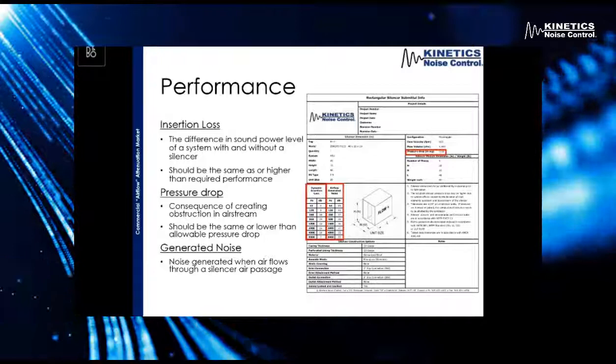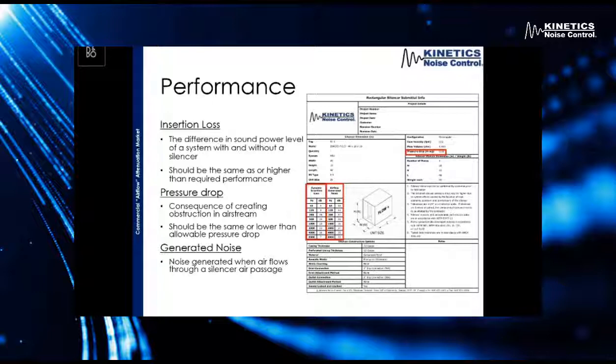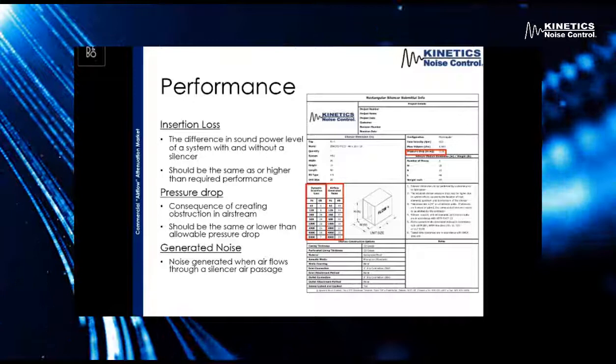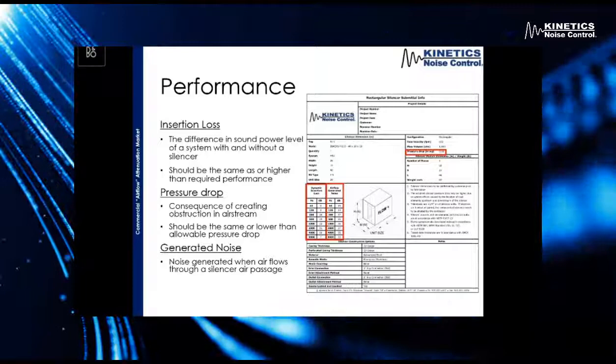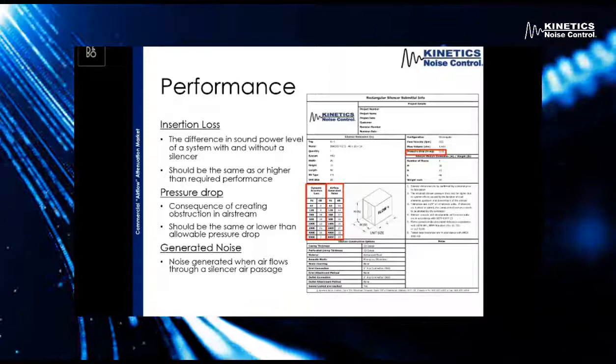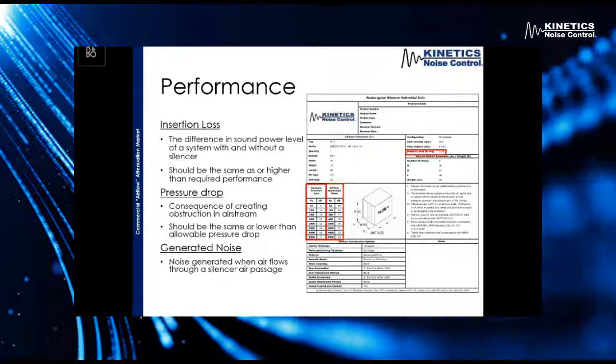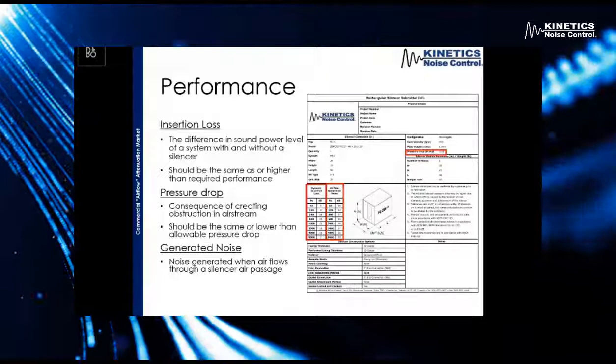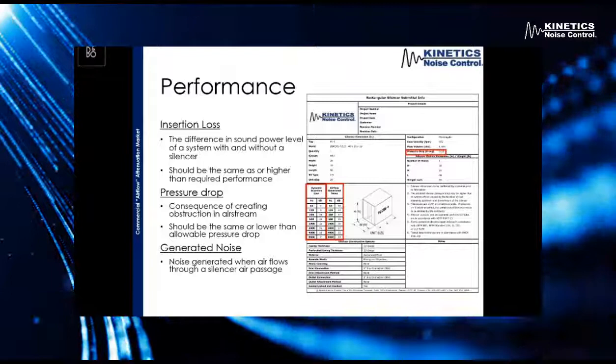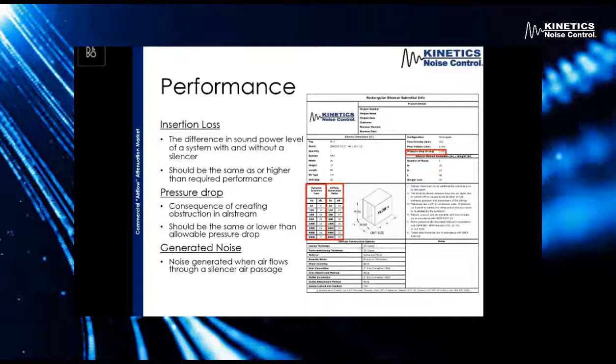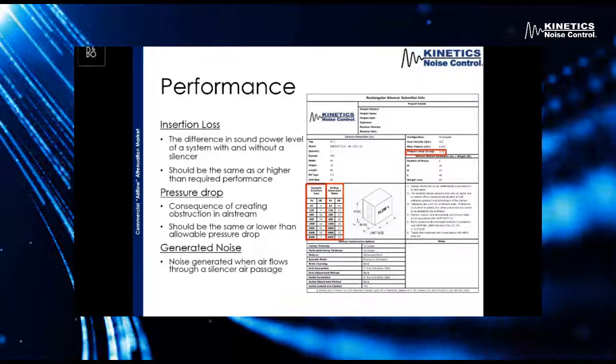We would want these insertion loss numbers to be the same or higher than what's required for a space. Next, we have pressure drop — this is the consequence of adding a silencer to the system. You don't get something for nothing. We're creating an obstruction in the airstream by adding the silencer, and that obstruction is going to cause a pressure drop. We measure it and list it on our submittals as well. Lastly, we have generated noise — the same way that the pressure drop is generated, we have turbulent airflow and an obstruction in the ductwork that causes some noise to be generated. For the most part, if we compare those generated noise numbers to the sound power levels of the unit the silencer is servicing, usually these numbers are quite a bit lower and negligible over the entire system.